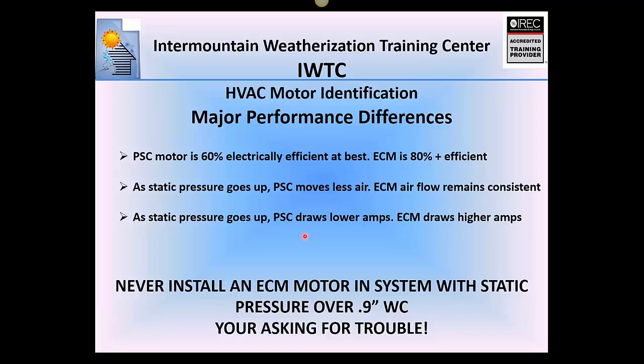Comparing performance: PSC motors are 60% electrically efficient at best — 60% of energy goes to work and 40% is converted to heat, which is why they have cooling holes and are inefficient. ECM motors are 80% and up efficient, don't produce nearly as much heat, and are better at converting electrical energy into mechanical work.